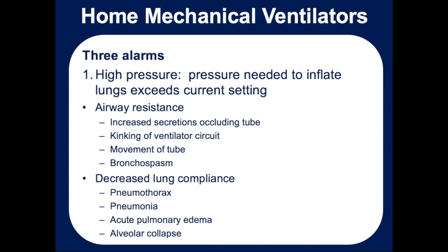Just understanding what that might mean will help you figure out what's going on with your patient. So you might encounter an alarm that says high pressure. Basically what the ventilator is saying is that in order to deliver the breath that it wants to deliver, it is sensing that it has to push too much pressure into the lungs to get that volume. That often happens because of some type of obstruction or resistance or decreased compliance in the lung. So the ventilator is having to push really hard to get the right amount of breath in. Some really simple things can be mucus plugs in the tubing, similar to the tracheostomy. If there's a mucus plug in the tracheostomy and the ventilator is pushing against that, that can cause an increase in pressure. If the ventilator circuit, which just means the airway tubing of the ventilator, is kinked, then that could create high pressure.